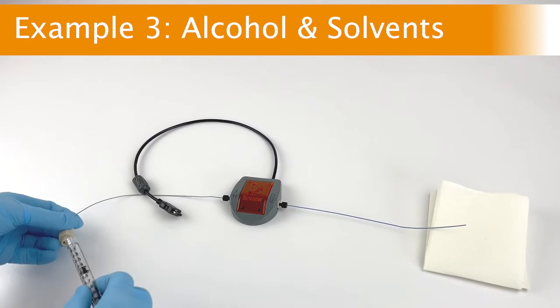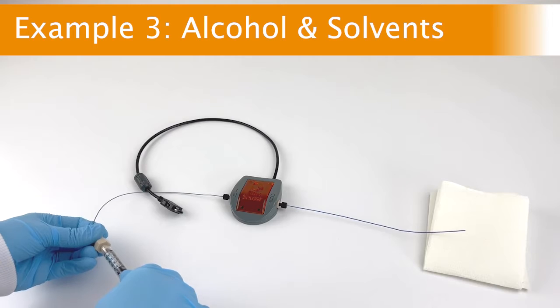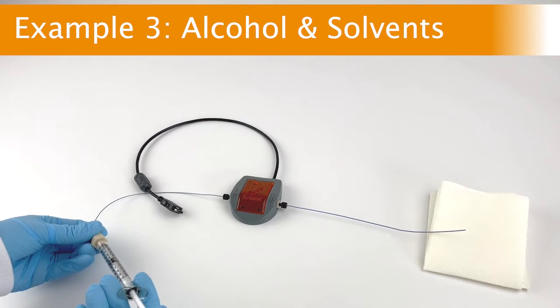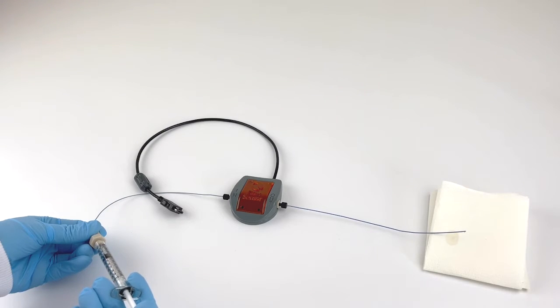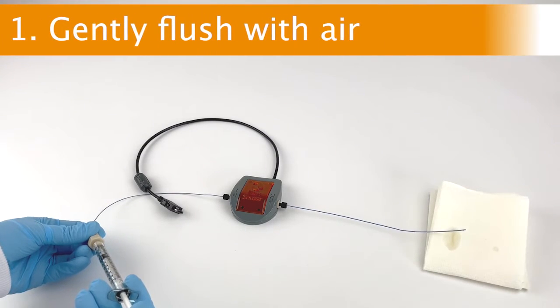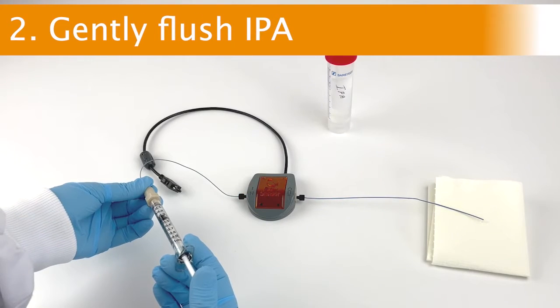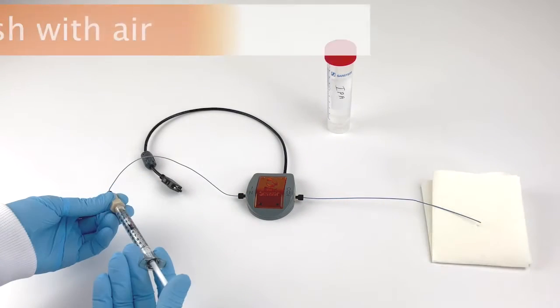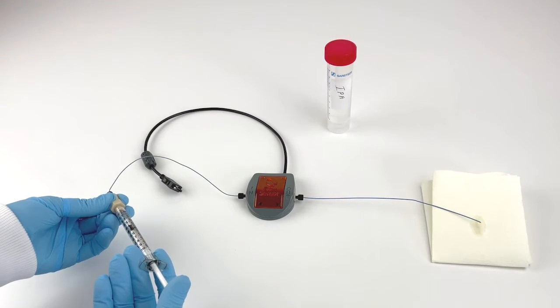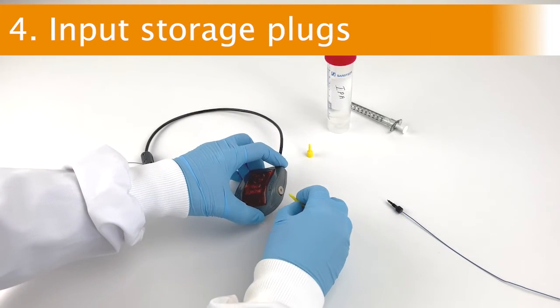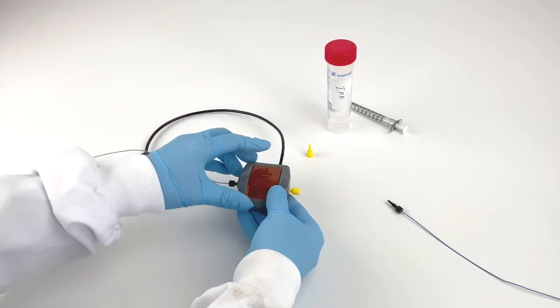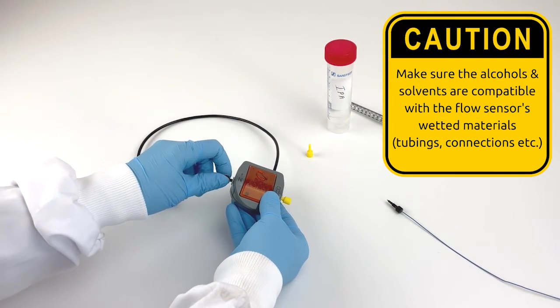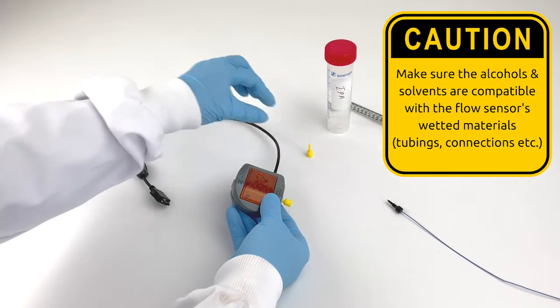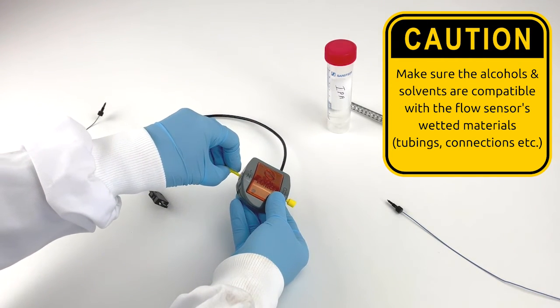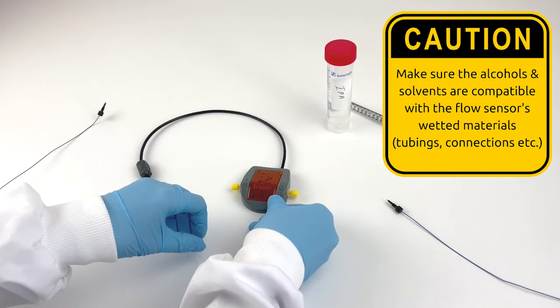Example 3. Working with alcohols or solvents. Unlike other liquids, alcohols and solvents are not critical and only require a short flush with IPA. The cleaning protocol is as follows. 1. Gently flush with air. 2. Gently flush with IPA. 3. Gently flush with air again. 4. Close the input and output ports to the flow sensor with the plugs provided and store. Caution. Make sure the alcohols and solvents are compatible with the flow sensor's wetted materials, tubing, connections, etc.